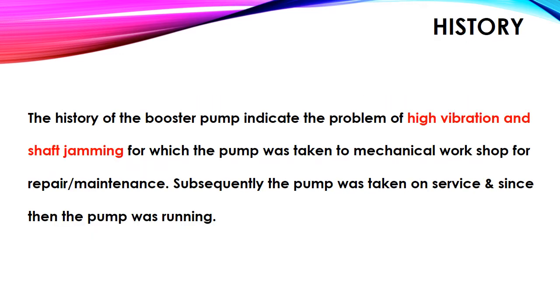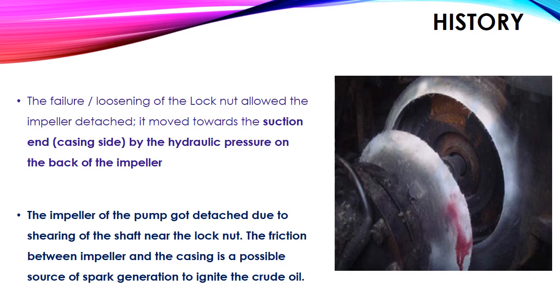The history of the booster pump indicates the problem of high vibration and shaft jamming, for which the pump was taken to the mechanical workshop for repair and maintenance. Subsequently, the pump was taken into service, and since then the pump was running. The loosening of the lock nut allowed the impeller to detach. It moved towards the suction end by hydraulic pressure on the back of the impeller. The impeller of the pump got detached due to shearing of the shaft near the lock nut. The friction between impeller and casing is a possible source of spark generation to ignite the crude oil.